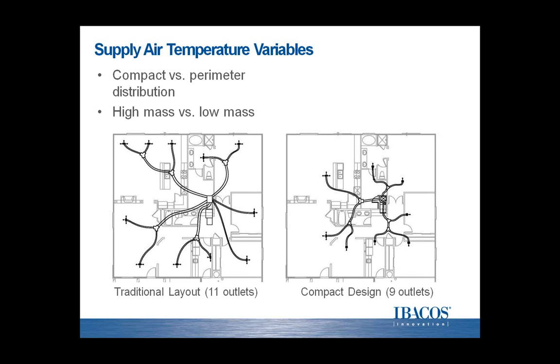that if that temperature that's going into that room is not being communicated to the thermostat and the space conditioning system isn't responding to that, then you can see very significant temperature swings. We've seen in Pittsburgh, in an unoccupied lab house we've had here, anywhere from 6 to 8 degree temperature differences, and these are on moderately warm or moderately cool sunny days. These are not peak load conditions by any means.